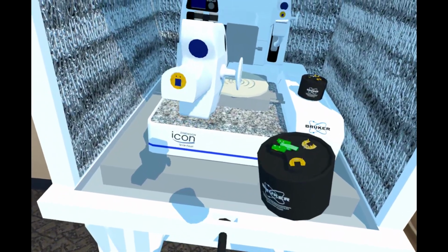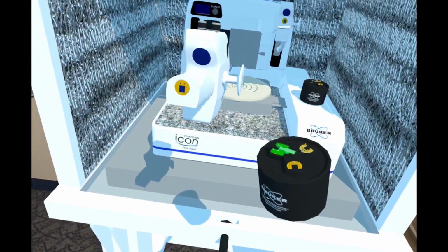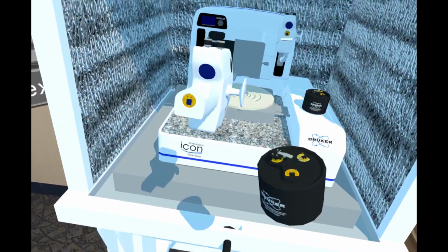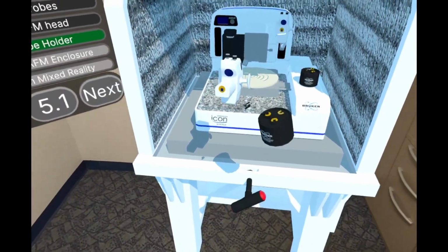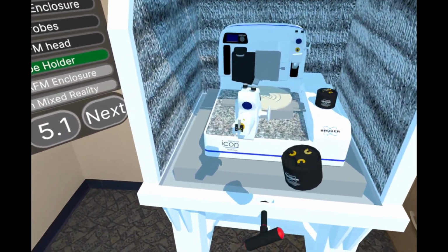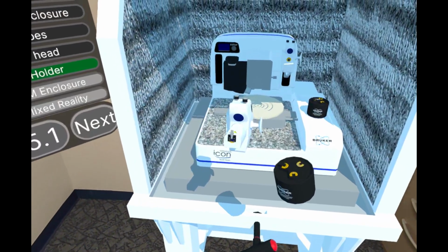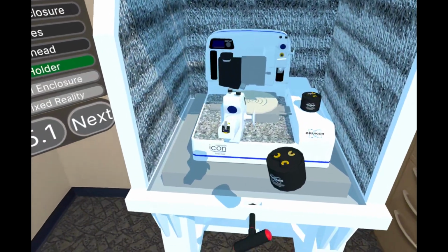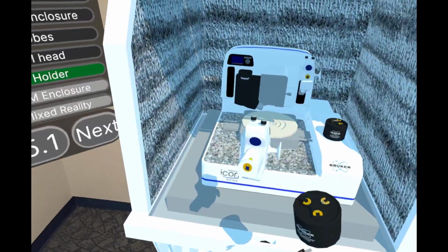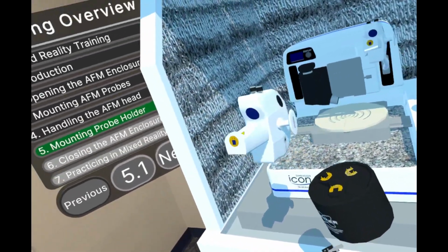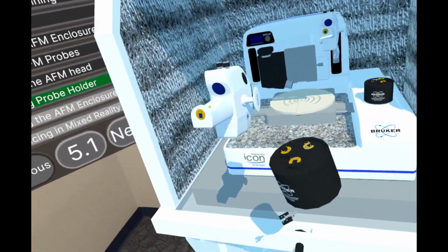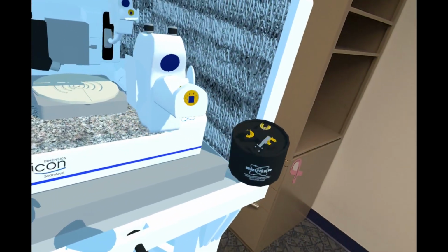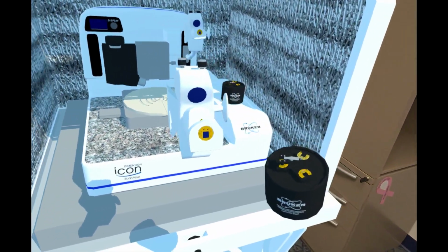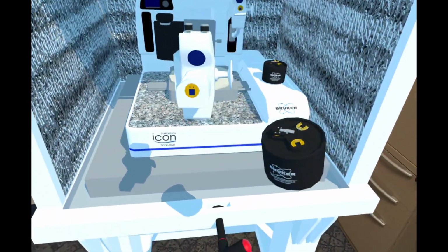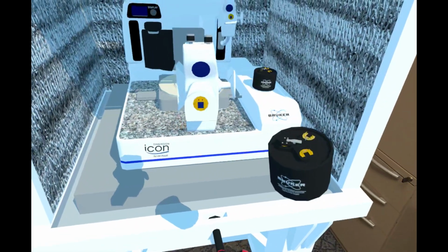Gently place the probe holder onto the head and lightly push down onto the pins, making sure it is all the way to the base of the pins and mounted flat. It might help to look at the pins from an underside angle to make aligning the pins with the probe holder holes easier. To replace the AFM head, lean into the enclosure and above the AFM. This will help you align the dovetail in the slot.